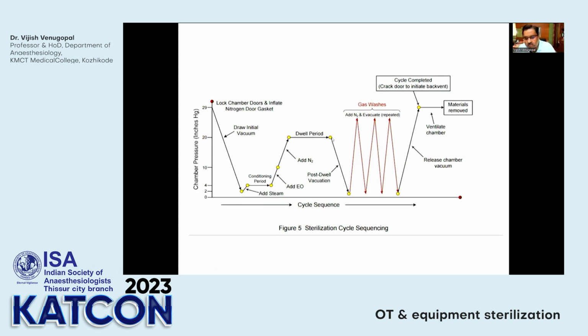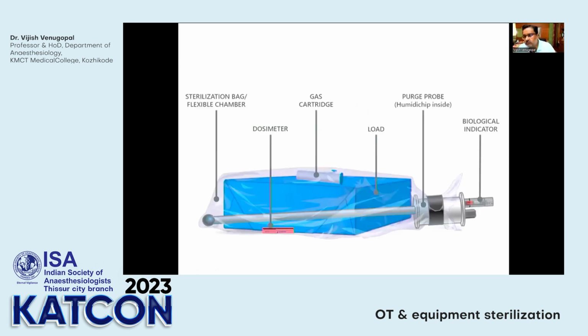And what it does here is there are gas washes that are given, air is given in and evacuated. So this is done repeatedly over the next 6 to 8 hours, and then it is ventilated outside. And this gas that is being sent out is poisonous. So it should be sent out high above the building. Okay, and then you can release the vacuum chamber, and the materials after ETO can be removed.